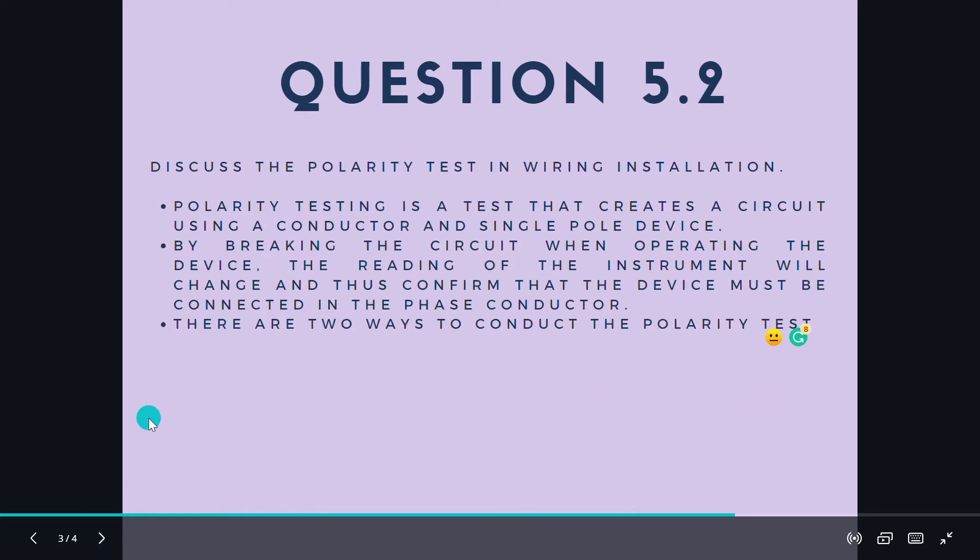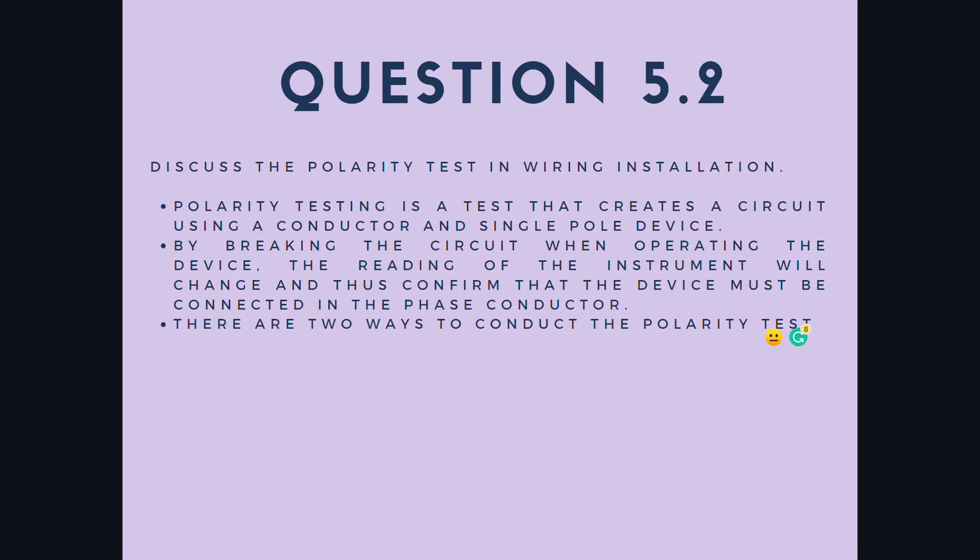For question 5.2, discuss the polarity test in wiring installation. Polarity testing is a test that creates a circuit using a conductor and single pole device. By breaking the circuit when operating the device, the reading of the instrument will change and thus confirm that the device must be connected in the phase conductor.